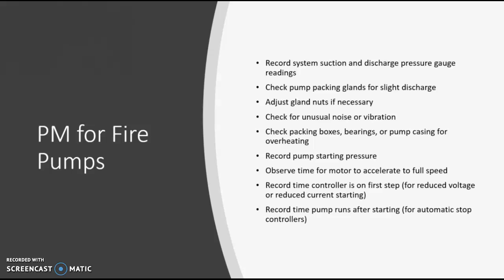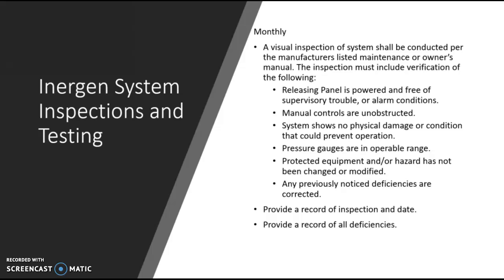Record the pump starting pressures. Observe the time of the motor for full speed. Record the time on the controller, and then check for your pump run times and whatnot, and actually record everything. Keeping a record is huge for preventive maintenance. The Inergen systems, any of the dry powder and dry systems are big on preventive maintenance and inspections.